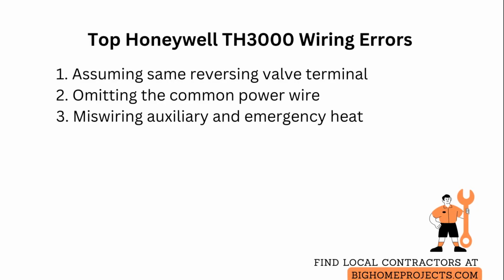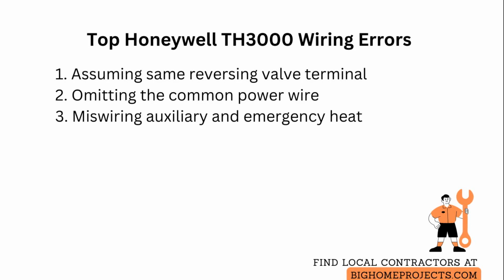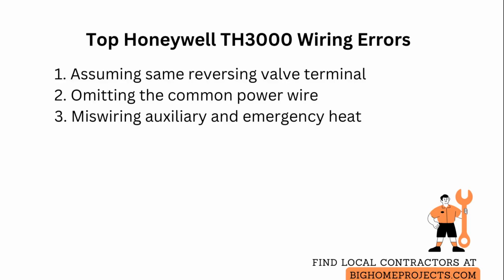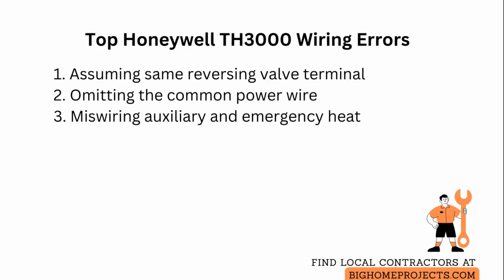People also sometimes wire auxiliary and emergency heat incorrectly by tying auxiliary to emergency terminals, which can prevent staged operation. Wire AUX for staged backup and E for true emergency only, and test both modes separately.